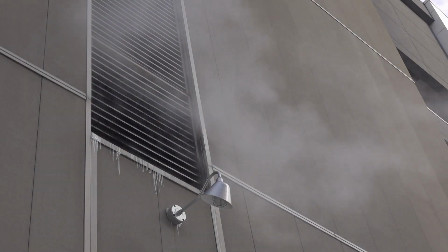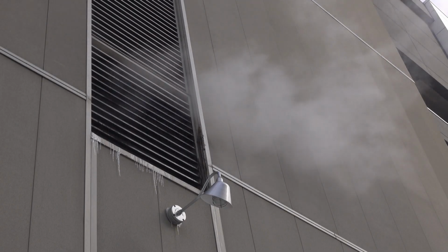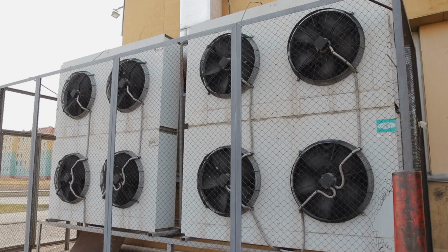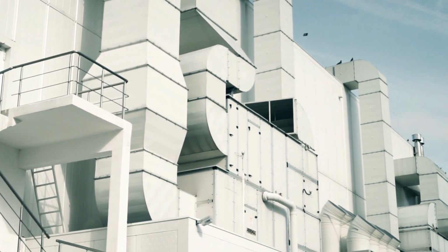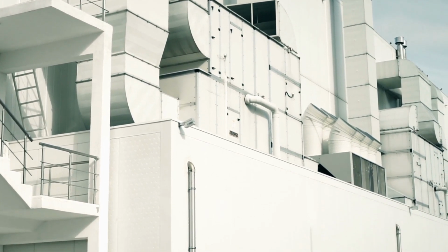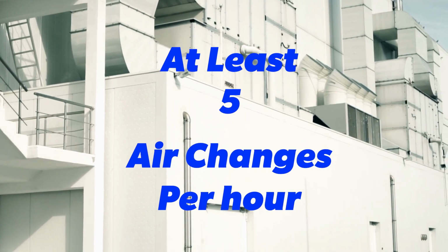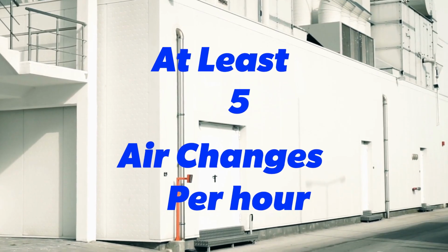Enhancing ventilation. Increasing ventilation is one of the most effective ways to reduce airborne virus transmission. The EPA suggests maximizing outside air ventilation by adjusting HVAC systems to increase fresh airflow. Redirecting airflows to minimize direct transmission, such as ensuring restrooms exhaust directly to the outdoors, can also help reduce recirculation of virus-laden air. The CDC recommends aiming for a ventilation rate of at least 5 air changes per hour, achieved through a combination of outdoor air and air treatment strategies.